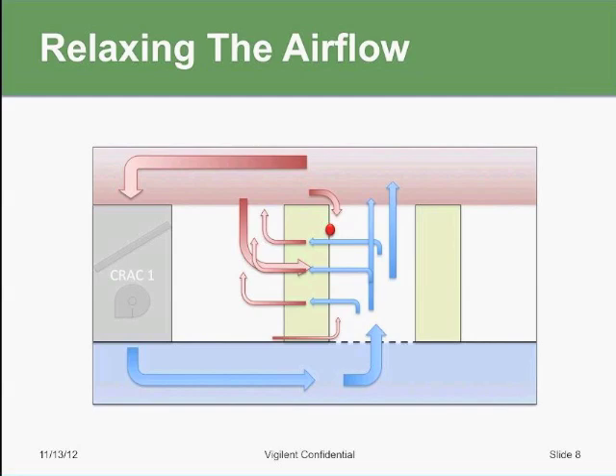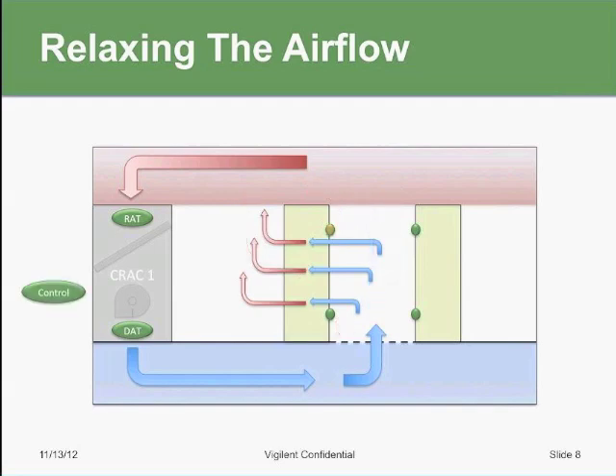And so how do we look at this and attack this from an operational perspective? Well, the first thing is you need to get data and measure the environment. And these green dots here indicate temperature sensors, measuring granular temperature data at the rack level. And you probably want to poll on a sub-minute frequency rate. And so you want to obtain information about the temperature in the thermal environment. And the next thing you want to do is obtain information about the cooling units themselves. So this shows a temperature sensor on the return air temperature and the discharge air temperature of every cooling unit. Now, once you have information about the thermal environment and also the cooling performance, then you can start to intelligently control the cooling to mitigate those hotspots and manage airflow in your facility. And it is through this vehicle that operational redundancy is achieved.